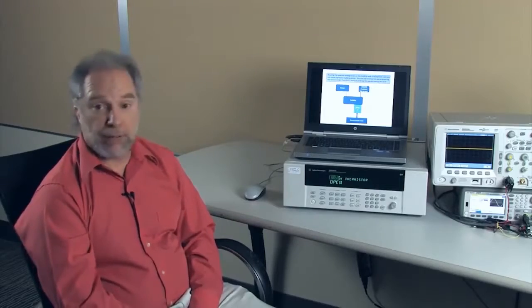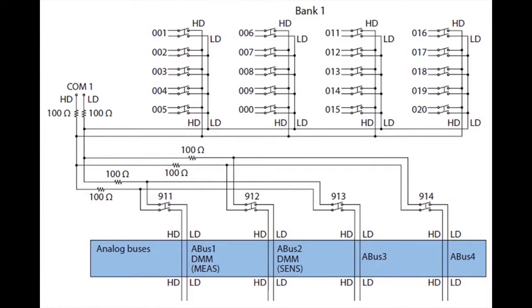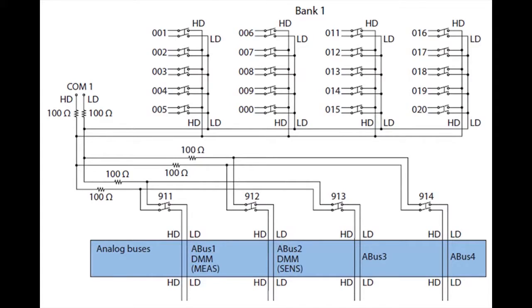One of the nice features about the 34980 is that you can add additional equipment by connecting signals to the rear of the box into the analog bus. We actually have four different analog buses that allow you to connect up to four different instruments.